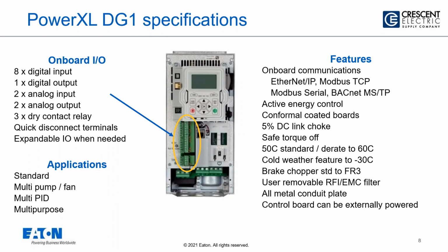We do have 4 different applications, and this is really nice from a standpoint that sometimes drives can be very daunting with the number of parameters in them. So what we'll do is we'll create applications which will pare out parameters that you really don't use, and we'll make it a lot easier to program. So we have a standard application, and that's going to be your pump, your fan, just anything that's kind of, I'm going to say, more than run of the mill, but it's I would say 90% of your applications.